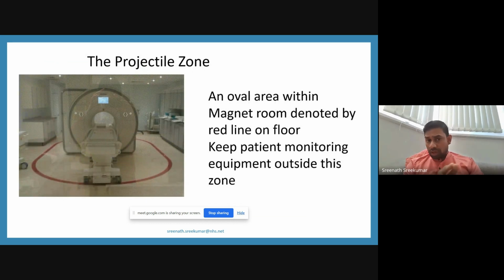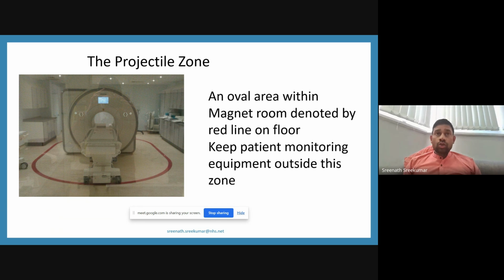Another thing we already discussed is the projectile zone. We can see it in the MR environment where the machine is situated. This is the projectile area where the maximum spatial gradient is exposed. The spatial gradient and fringe field are the two main things we have to discuss when discussing the magnet of the machine. The oval area within the magnet room denoted by a red line on the floor is called the projectile zone, where the maximum potential projectile risk of the machine is situated.